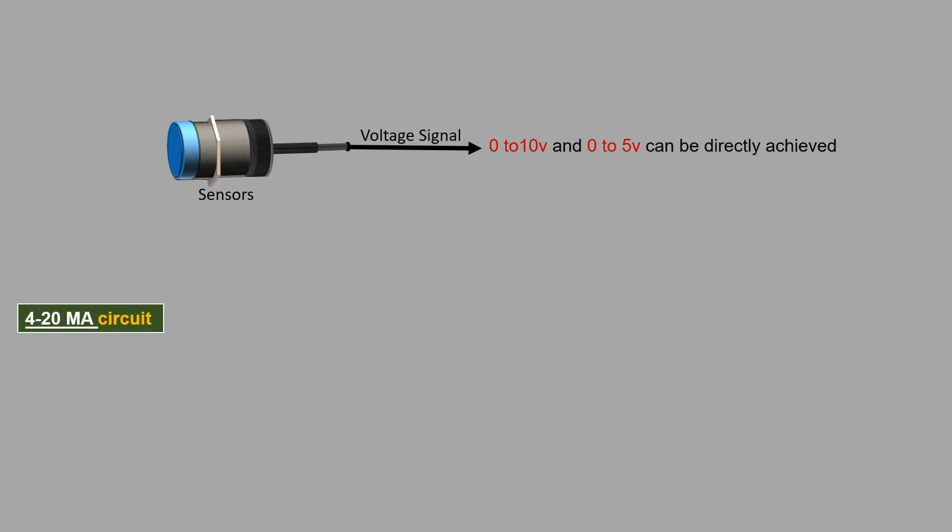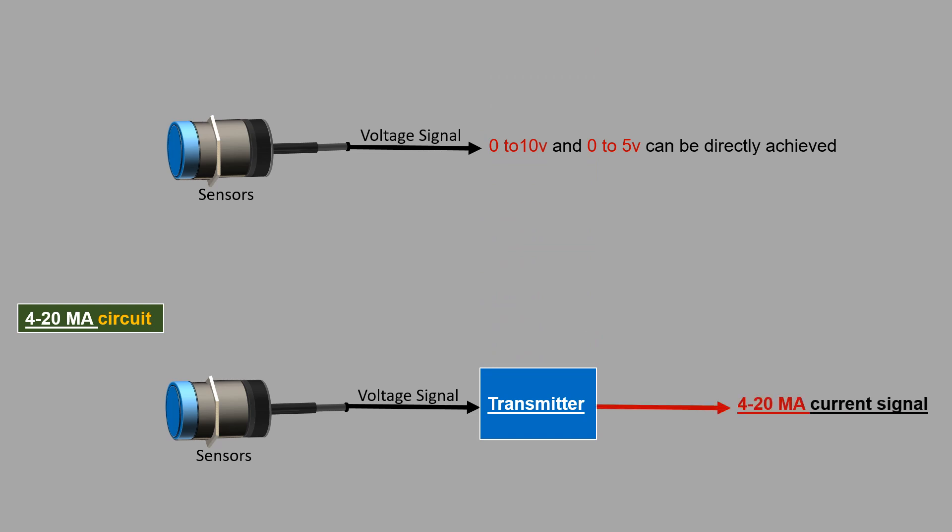Since most sensors naturally generate output in the form of voltage, 0 to 10 volt and 0 to 5 volt outputs can be directly achieved. In 4 to 20 mA circuits, the voltage output of the sensor is sent to a transmitter which will convert the voltage signal into a current signal.